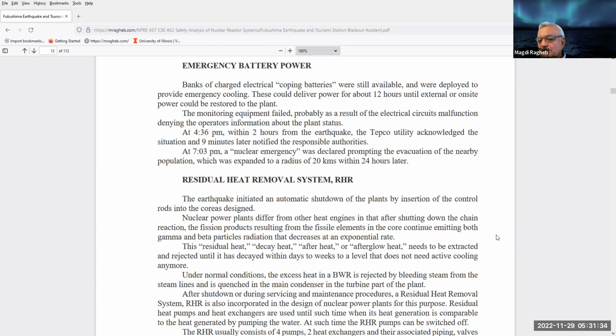For emergency at nuclear power plants, to provide controls even if the power is lost, they have what they call coping batteries. They were still available, and were provided to provide emergency cooling. These could deliver about 12 hours until external power - it gives time, winning time - until external or on-site power could be restored to the plant.